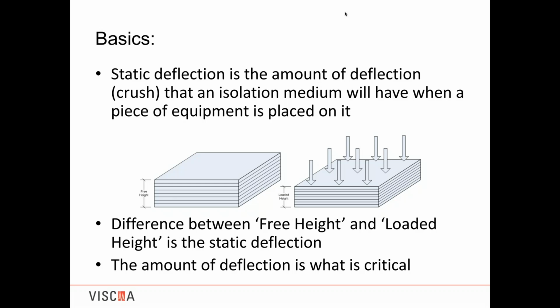Now, just deflecting by itself doesn't necessarily make it an isolator. The medium that you're using, after you remove the load, needs the ability to come back to its free height. If after loading it, you remove the equipment and it stays where it was, it now doesn't have any static deflection. So the medium can't just be anything that squishes and stays. There are some materials that as you push on them, they stay and don't come back. That's not what would be considered an isolator.